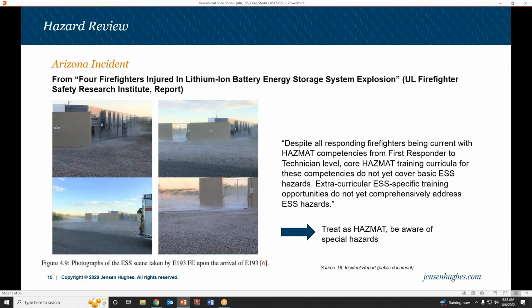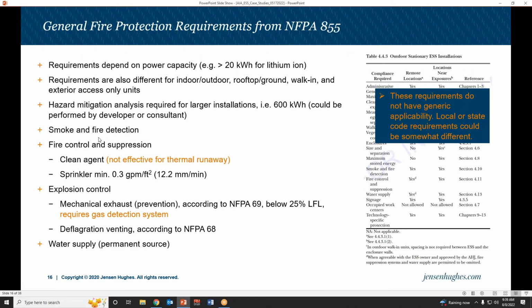I want to show you some pictures from this incident, when the fire department responded, and encountered this white type of fog or smoke. Luckily, they were suspicious and pulled out their gas monitors right away and did some measurements, and saw there's a lot of nasty stuff in the air. So they defined a no-go area and monitored the installation for a few hours before they made entry. But this is how that could potentially look like.